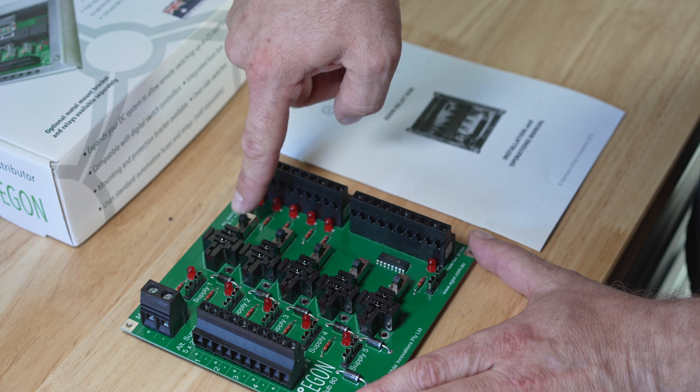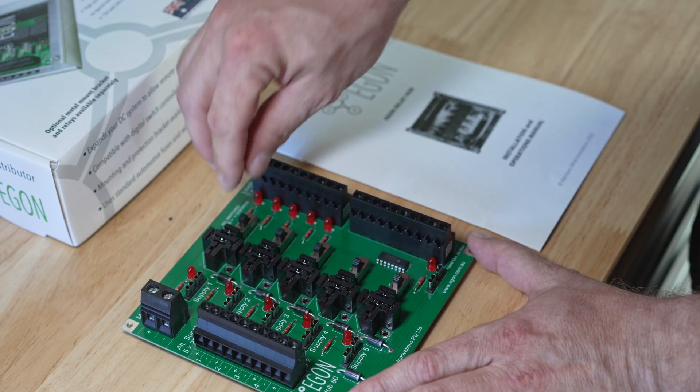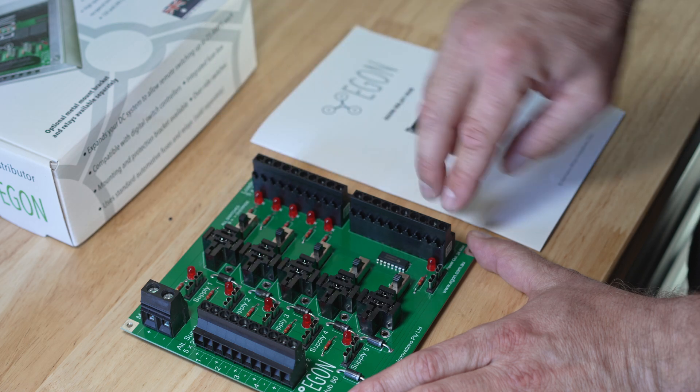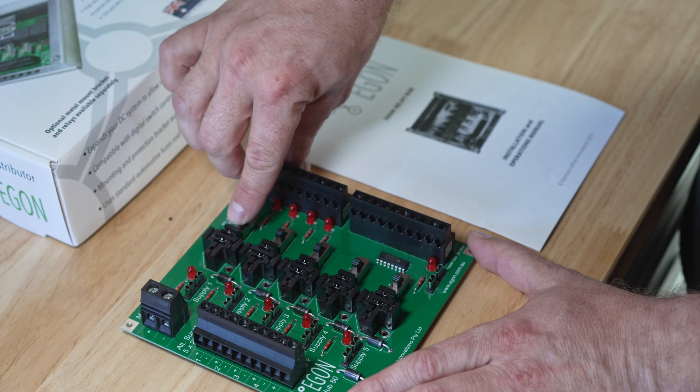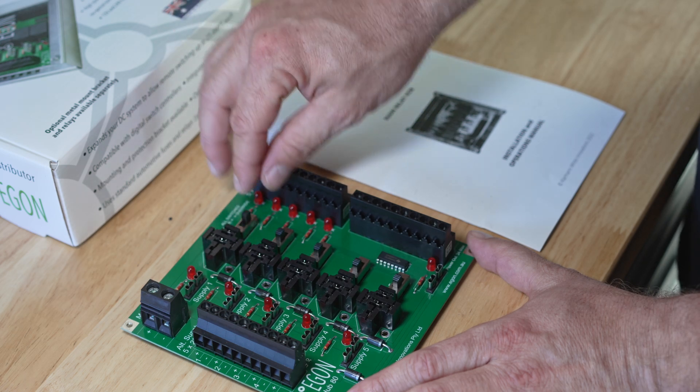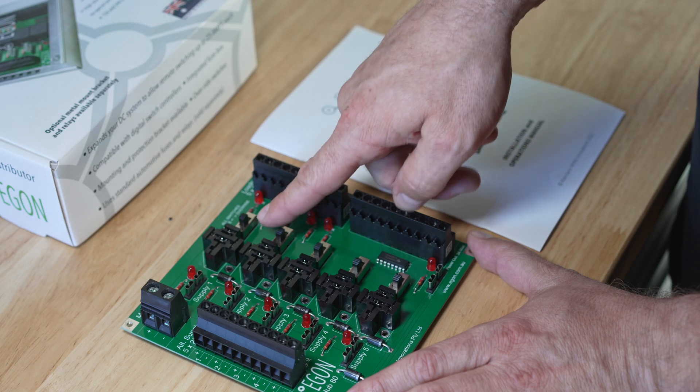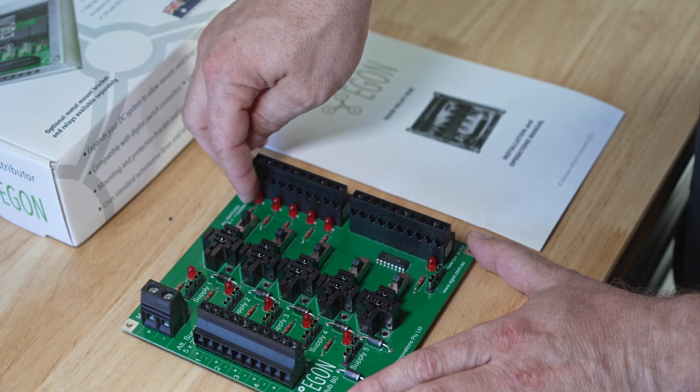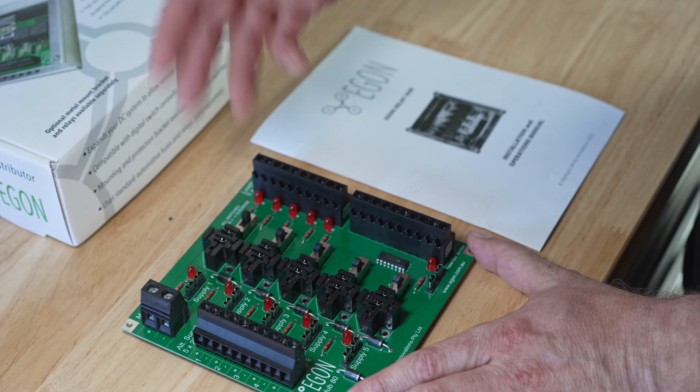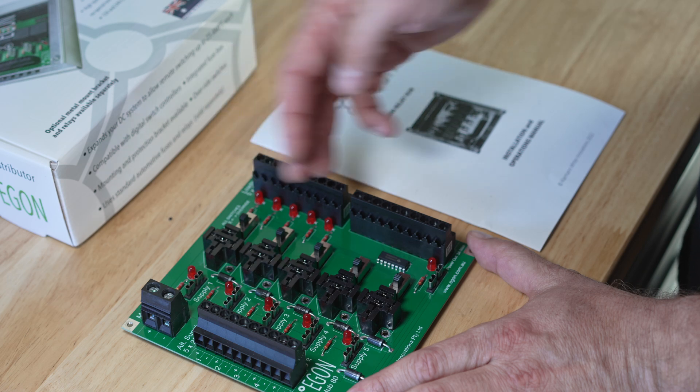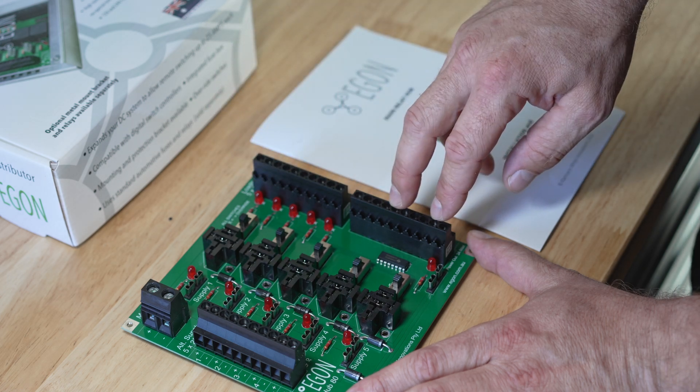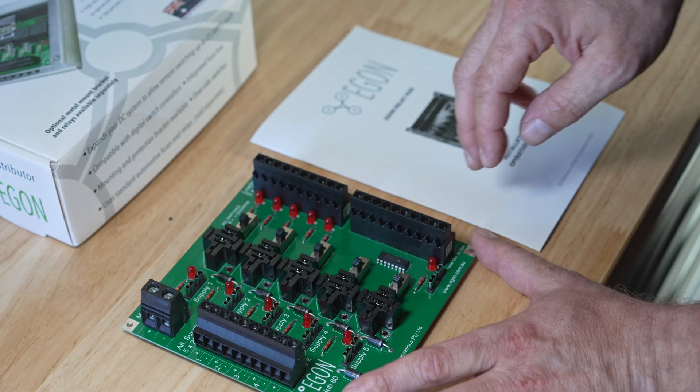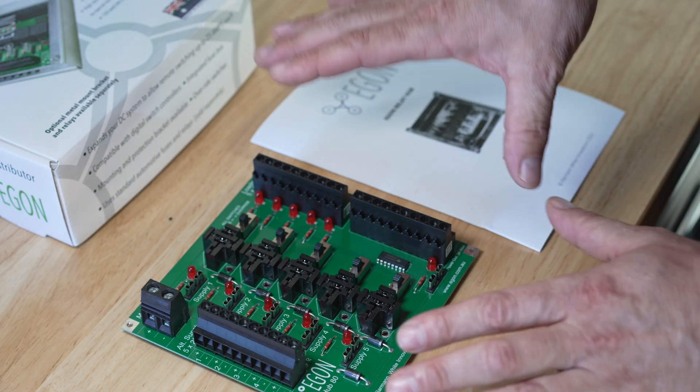You also find that there's a switch right next to each relay. These are override switches just in case your external switching fails for whatever reason. You've got an override switch on the board to activate the output. This is quite handy for fault finding because as soon as you turn something on here you will see the LED turning on. You know your power supply and your relay are still working and you can work backwards to see if either the switch circuit is faulty or the power supply is faulty. So fault finding measures are built in to this board.